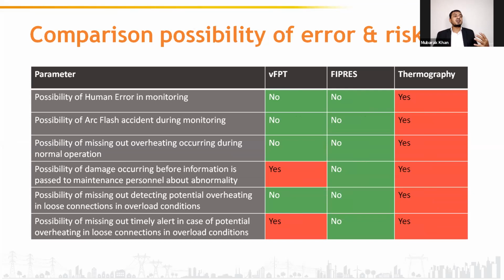Now, comparison of the possibility of errors and risks. Possibility of human error during monitoring: in VFPT and FIPRES, it's not possible. In thermography, yes, it is possible. Possibility of an arc flash accident during monitoring: in thermography, yes, it is possible because you are doing monitoring in live panels. But in VFPT and FIPRES, it is not possible. Possibility of missing overheating occurring during normal operation: in VFPT and FIPRES, not possible. In thermography, yes, it is possible.